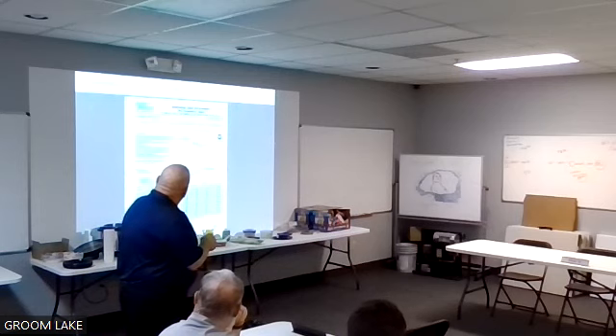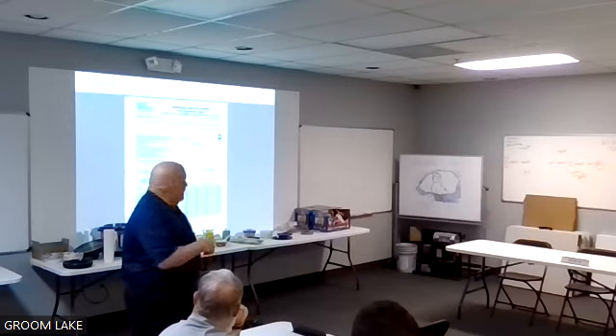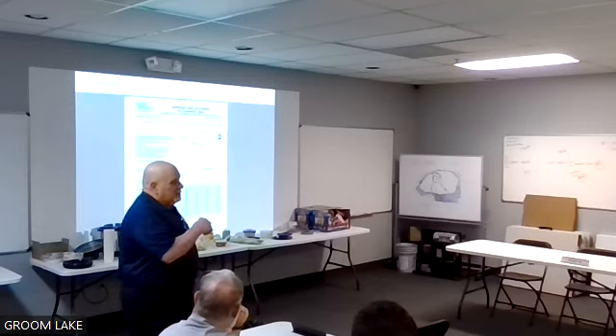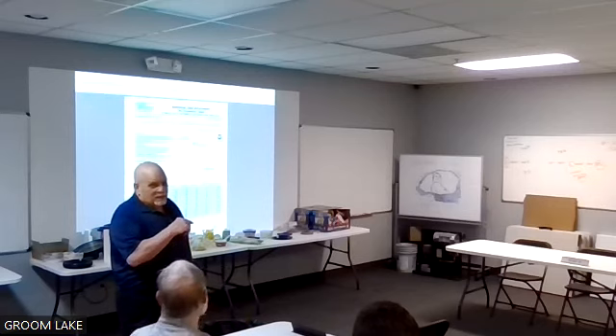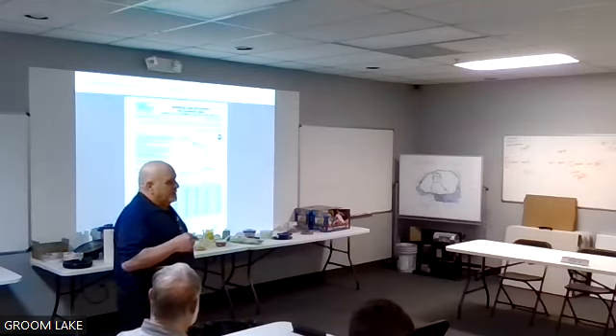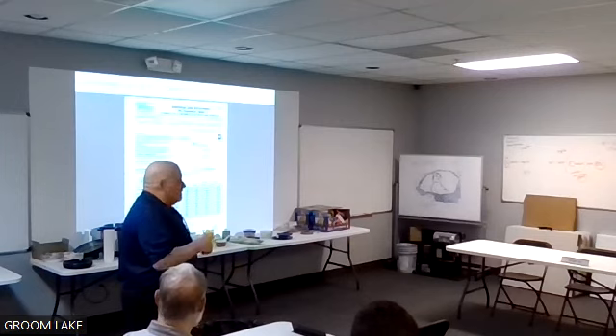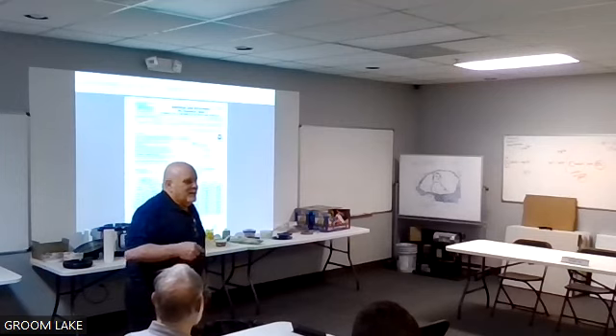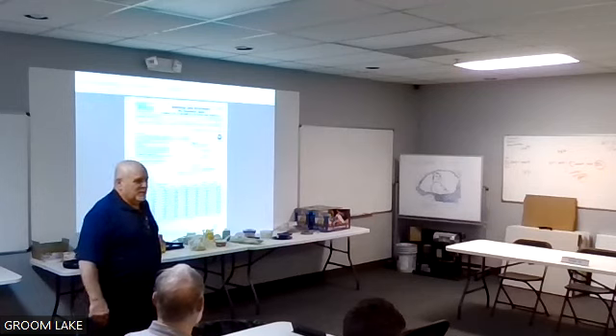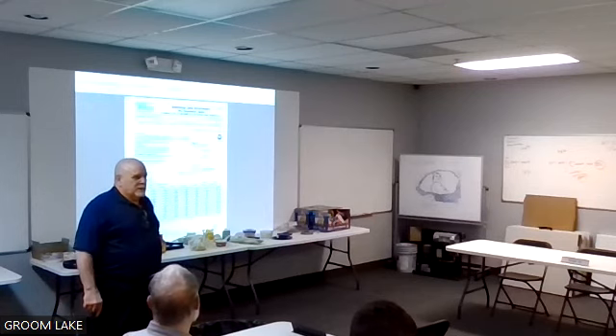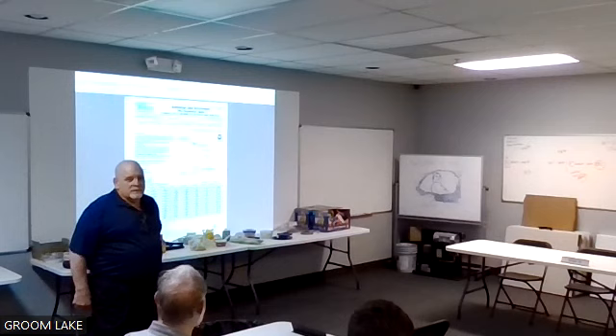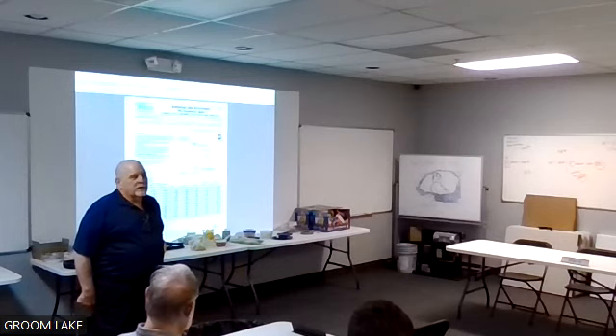When you have that NSF 61 certification, you guarantee it's no lead. The exact same tank comes off the line. It's not lead, it has no lead either. The only difference is I don't have a piece of paper to go with it. So you can use the standard ones. We stock all NSF now, just erring on the side. But there's a lot of people out there that put the regular one in, and a lot of the inspectors don't even pay attention to it. But I mean, it's still lead free. You're not endangering your customer. You have a piece of paper. Any questions on that?